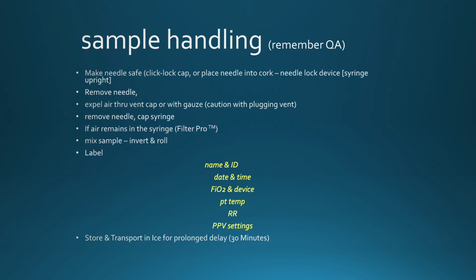If air remains in the syringe, it's best to use devices. One commercial device is called Filter Pro, and it's a little cap that goes on. It has a porous material in the cap that allows air to exit but will not allow the blood to exit. Mix the sample by inverting or gently rolling it, and that mixes the lyophilized heparin and extends the useful life of that sample before a coagulation could occur.